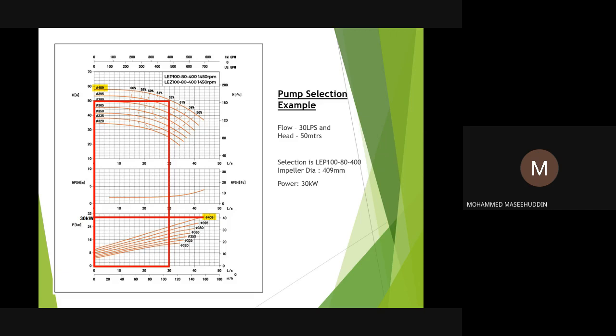If you see the corresponding kilowatt rating, which is mentioned on the y-axis at the bottom of the curve, if you look at the motor curve, which is for the kilowatt rating, at the duty condition, the absorbed power is 24 kilowatts at 30 liters per second and 50 meters.